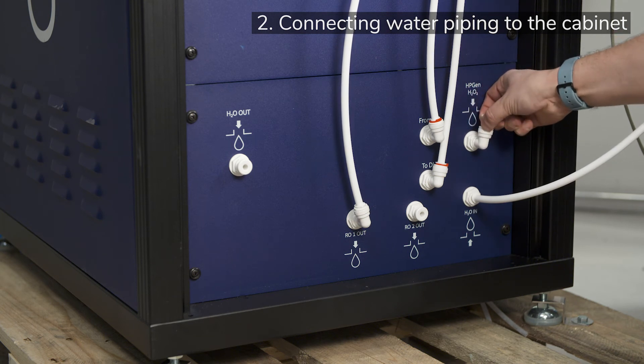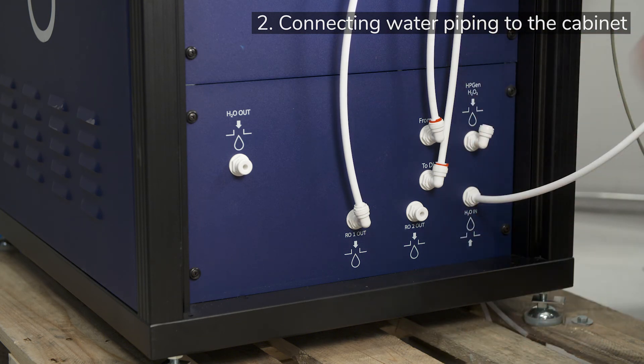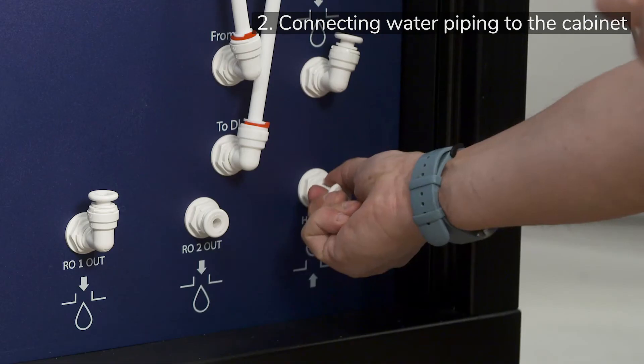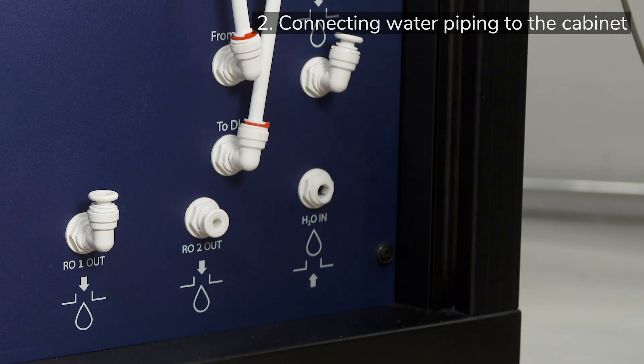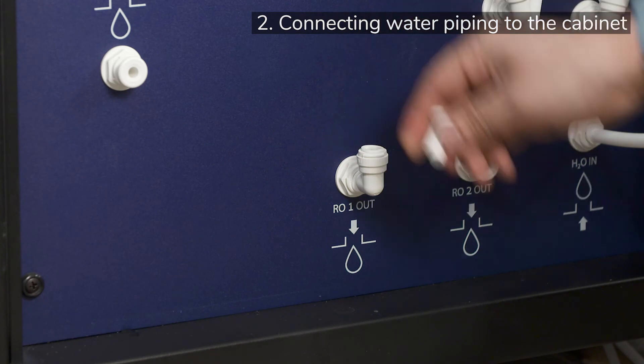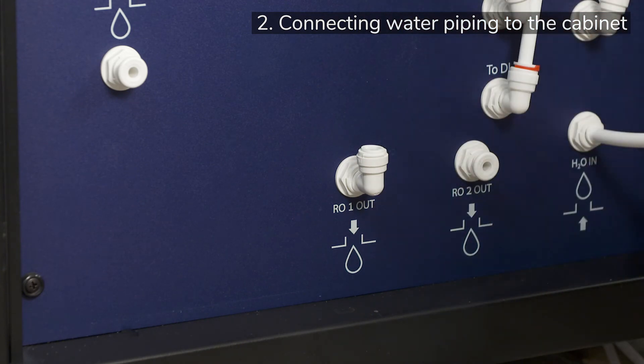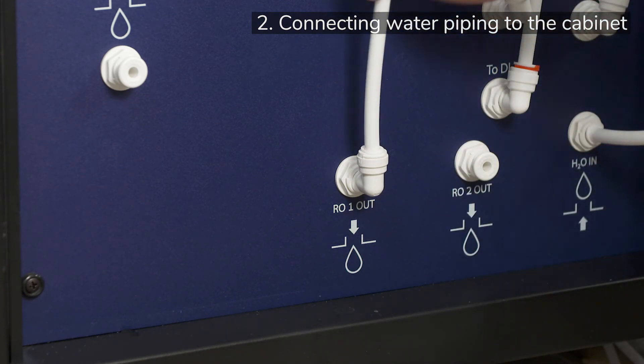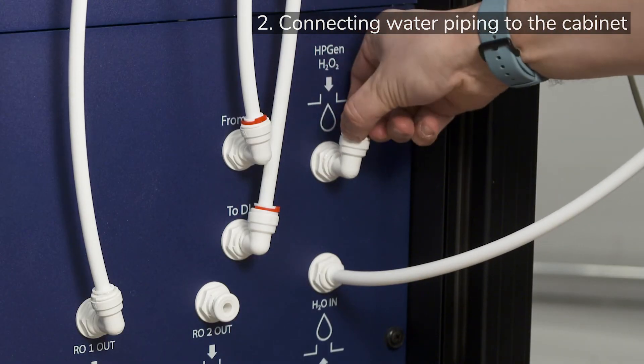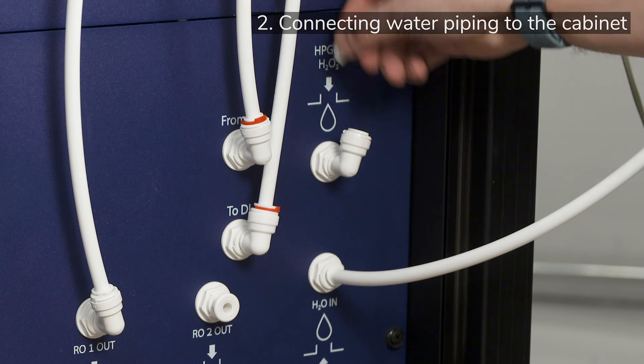To insert a tubing in the quick fitting, simply insert the tube all the way and check that it cannot be pulled out again. In the bottom right corner, connect your water source where it says H2O in. Next, connect tubing to the bottom left fitting, labelled RO1, which should be connected to a drain.